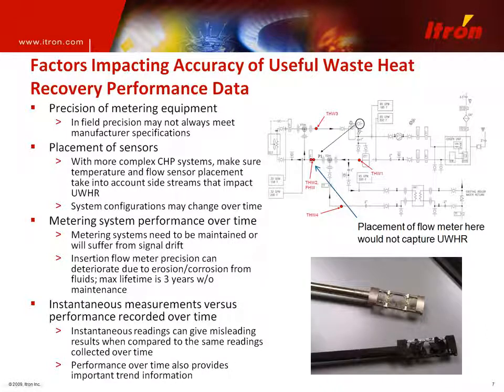Without maintenance, what we've generally seen in California is the turbine meter life tends to peter out after about 3 years. It's also important, sometimes when people are commissioning CHP facilities, they take instantaneous readings, or they come back and they want to look at the useful waste heat recovery at a particular point in time. Well, you might get a very different indication of how the system is performing if you're looking at an instantaneous reading versus looking at performance over time. And that also provides you some very important trend information.